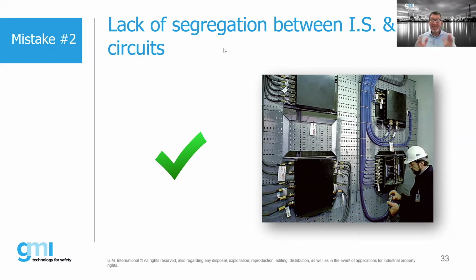But anyhow, within the same cable duct, you need to keep a separation of 50 millimeter. But if you run two different cable ducts, can they be next to each other? Generally speaking, we would have those ducts at least 50 millimeters apart, so we can visually tell that we've maintained that 50 millimeter separation. There's nothing in the standards for the most part that says we cannot run IS and non-IS in the same duct, but it would have to be a very wide duct, and we would have to bundle the IS on one side and the non-IS on another side and make sure that we're keeping that separation.